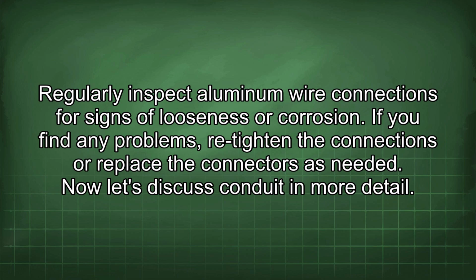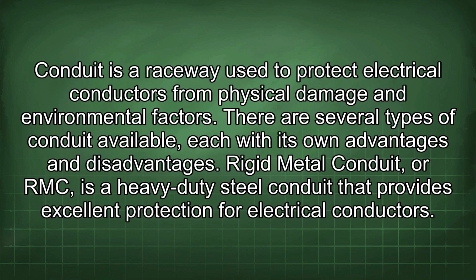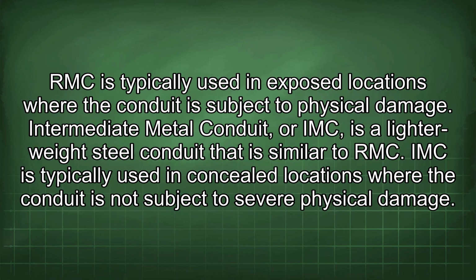Now let's discuss conduit in more detail. Conduit is a raceway used to protect electrical conductors from physical damage and environmental factors. There are several types of conduit available, each with its own advantages and disadvantages. Rigid metal conduit, or RMC, is a heavy-duty steel conduit that provides excellent protection for electrical conductors. RMC is typically used in exposed locations where the conduit is subject to physical damage. Intermediate metal conduit, or IMC, is a lighter weight steel conduit that is similar to RMC. IMC is typically used in concealed locations where the conduit is not subject to severe physical damage.